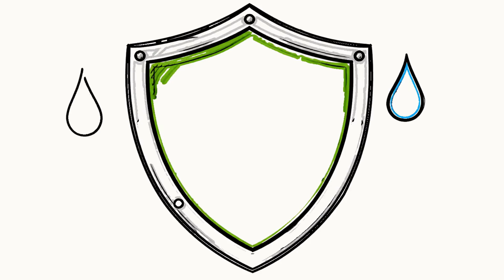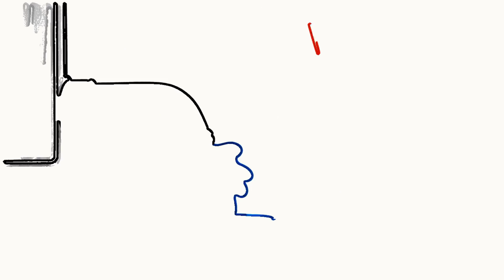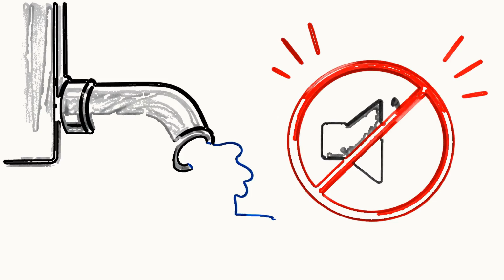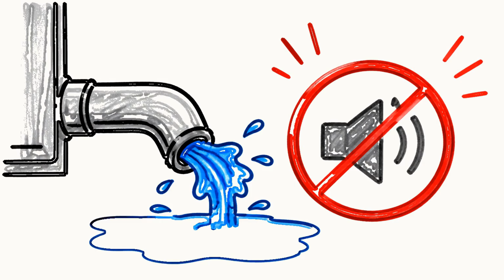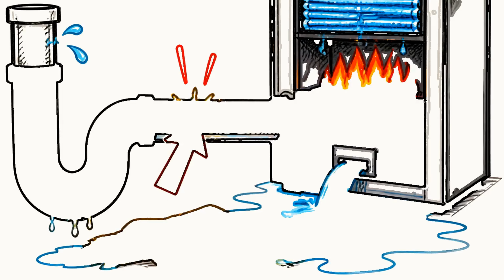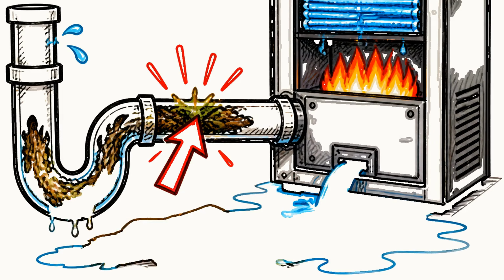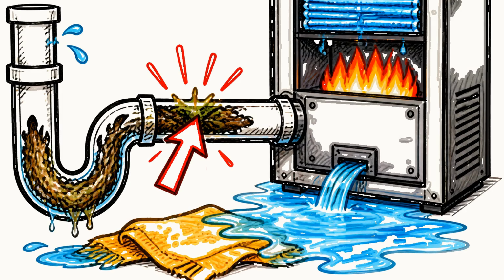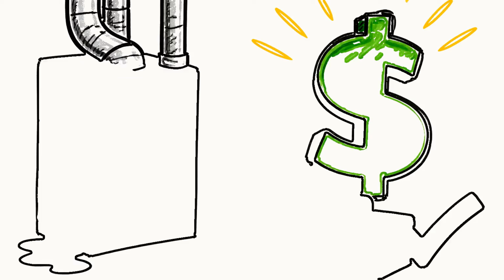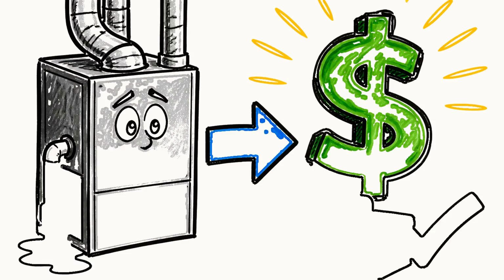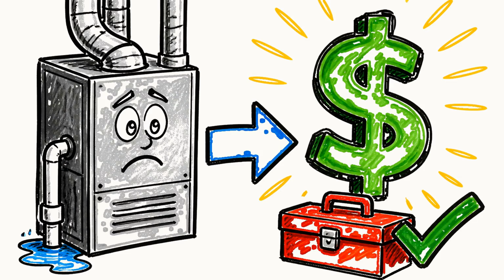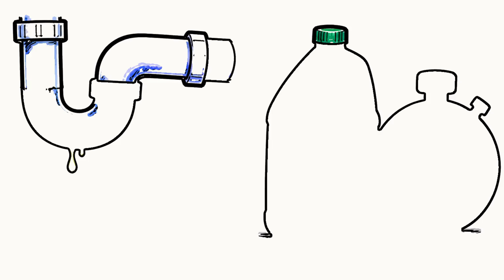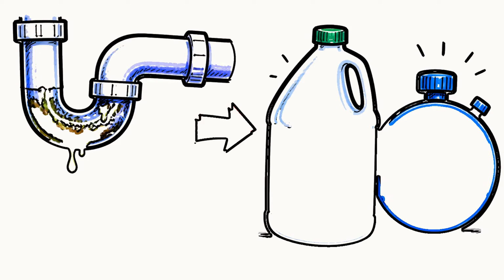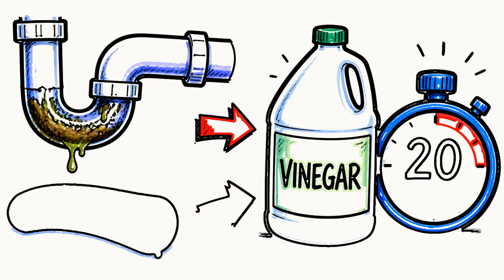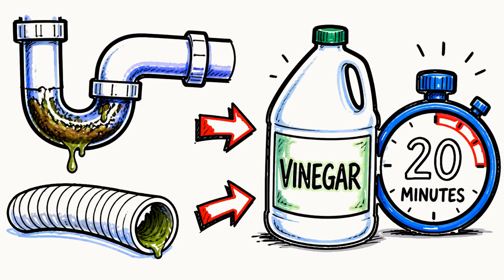So the water itself is usually not your problem. The problem is that the water is supposed to drain away quietly, and right now it is not. Something in the drain path is clogged, broken, or backed up, and the overflow is what you are mopping off the floor. That is the reassuring part, because a drainage problem is one of the cheapest things that can go wrong with a furnace. Most of the time you are looking at a clogged plastic trap or a slimed up hose, and the fix costs you a jug of vinegar and 20 minutes.